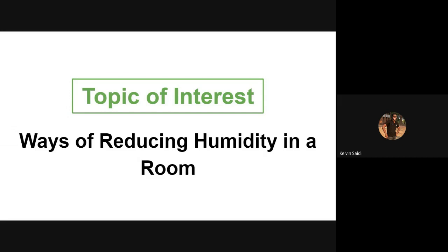But as earlier mentioned, high humidity negatively affects oxygen concentrators in general. When you are undertaking oxygen concentrator repairs and maintenance, there might be a need for refilling the sieve beds with new zeolite. As most of us know, zeolite is a substance that has a high affinity for moisture, and when it absorbs this moisture, it degrades. This implies that it will lose its ability to separate the nitrogen from the air efficiently, and it will lead to low oxygen purity for our machines.